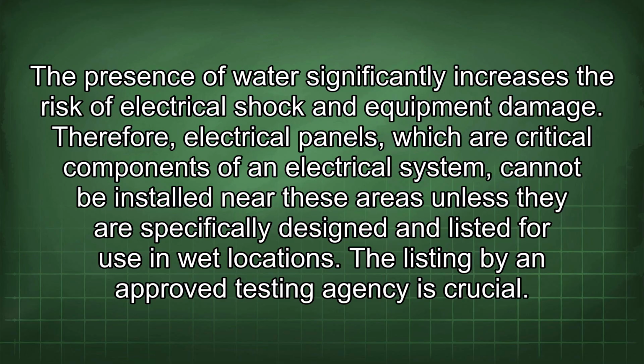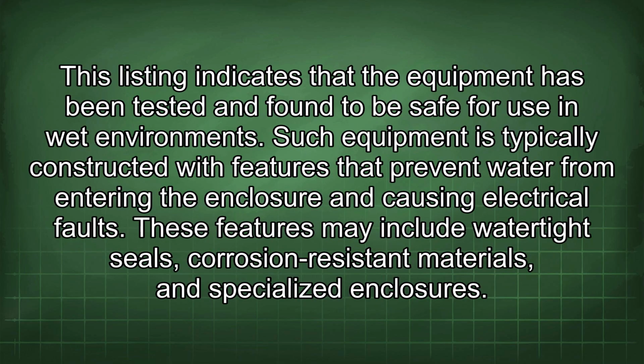Therefore, electrical panels, which are critical components of an electrical system, cannot be installed near these areas unless they are specifically designed and listed for use in wet locations. The listing by an approved testing agency is crucial. This listing indicates that the equipment has been tested and found to be safe for use in wet environments. Such equipment is typically constructed with features that prevent water from entering the enclosure and causing electrical faults. These features may include watertight seals, corrosion-resistant materials, and specialized enclosures.